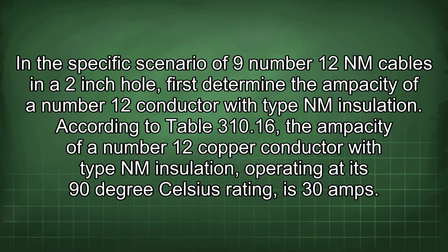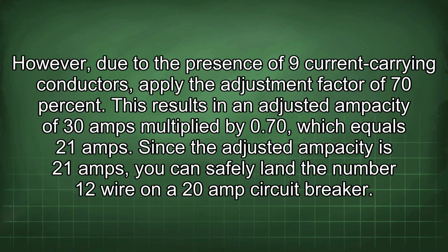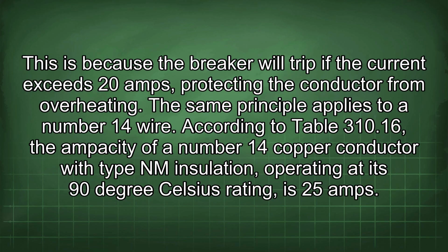a number 12 conductor with type NM insulation. According to Table 310.16, the ampacity of a number 12 copper conductor with type NM insulation, operating at its 90°C rating, is 30 amps. However, due to the presence of 9 current-carrying conductors, apply the adjustment factor of 70%. This results in an adjusted ampacity of 30 amps multiplied by 0.7, which equals 21 amps. Since the adjusted ampacity is 21 amps, you can safely land a number 12 wire on a 20 amp circuit breaker. This is because the breaker will trip if the current exceeds 20 amps, protecting the conductor from overheating.